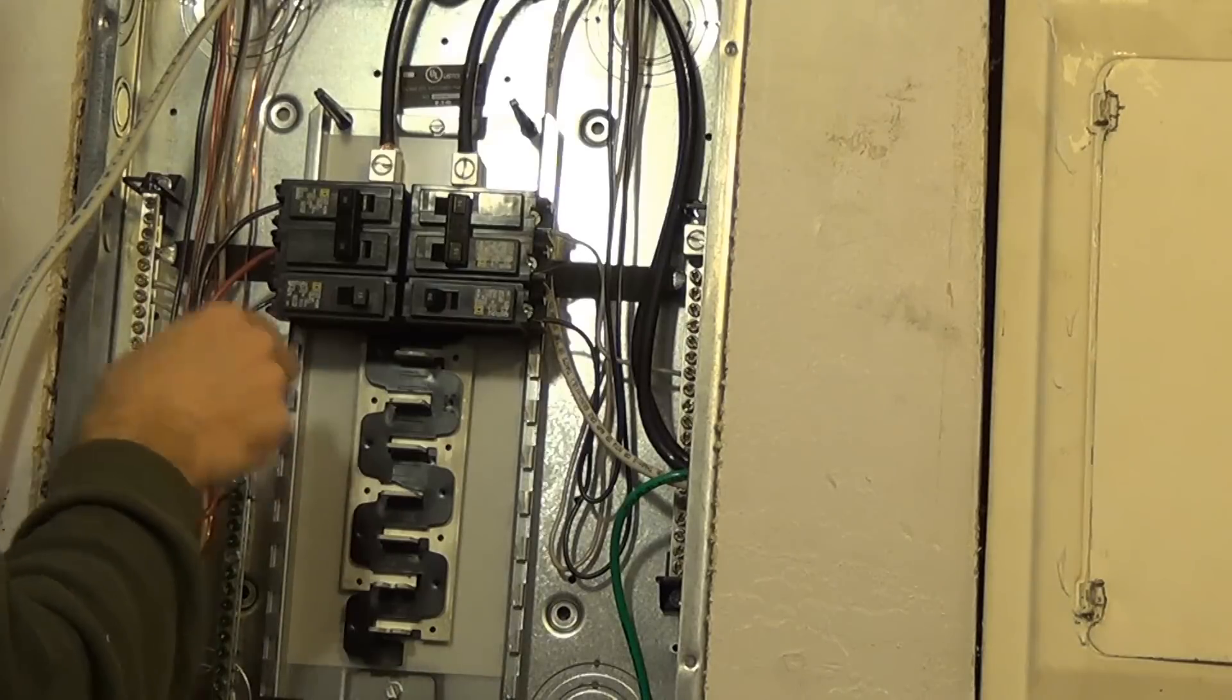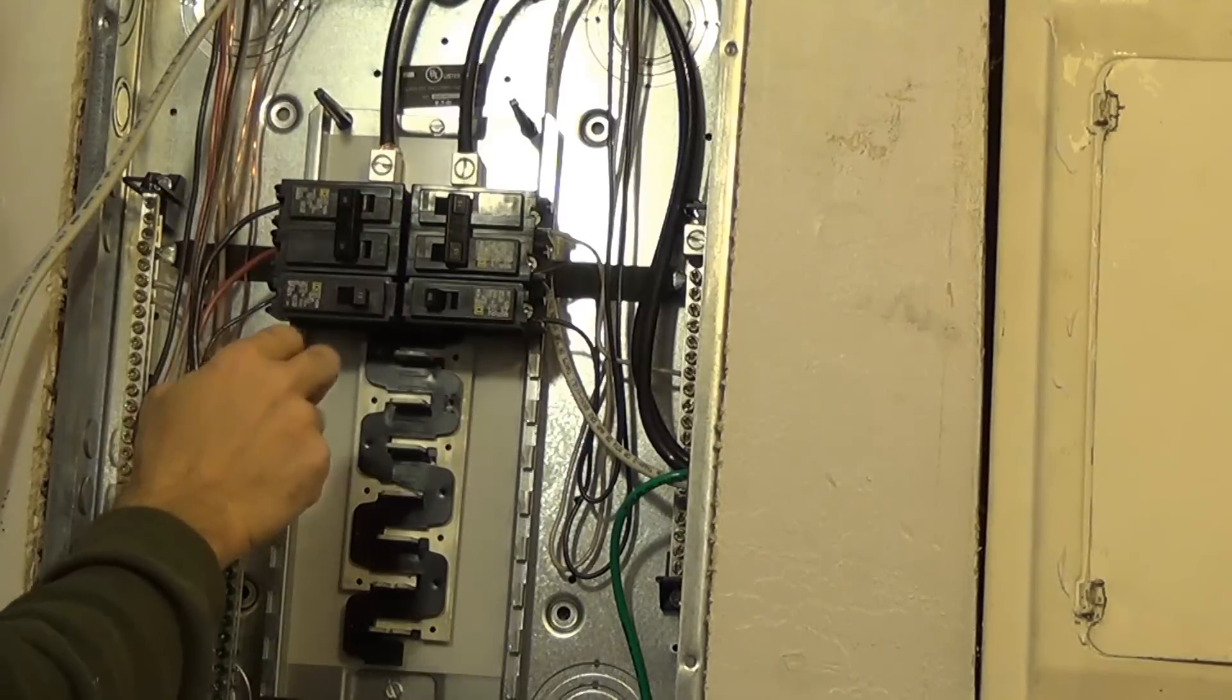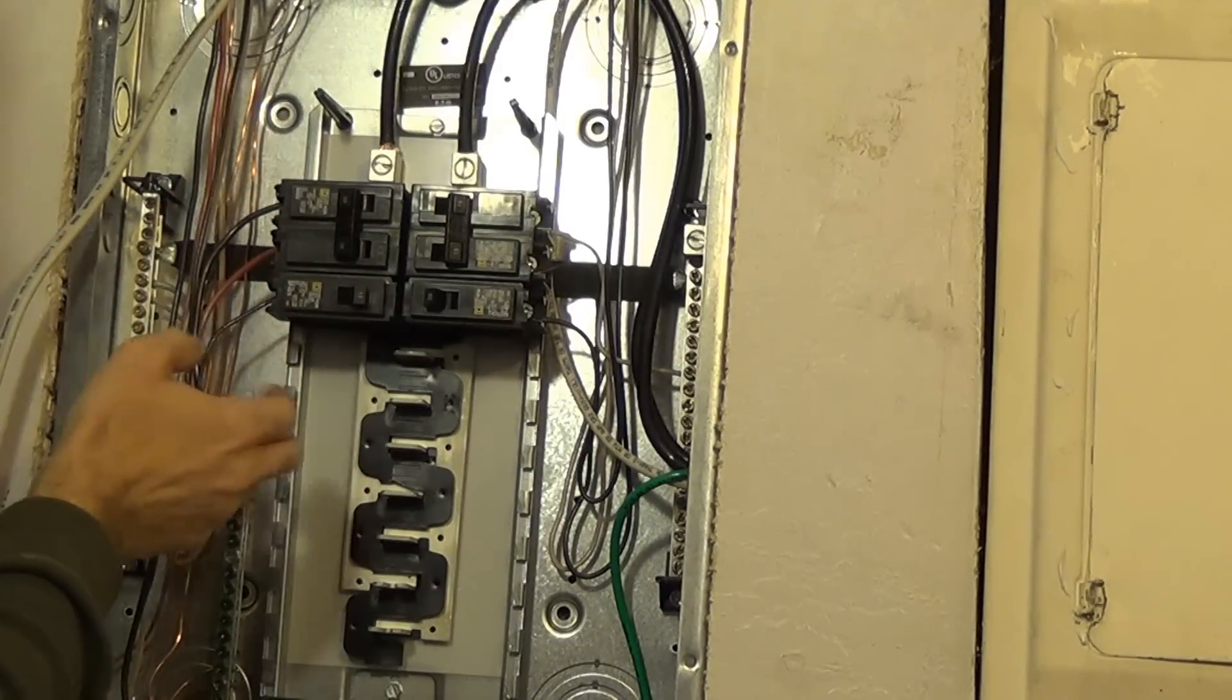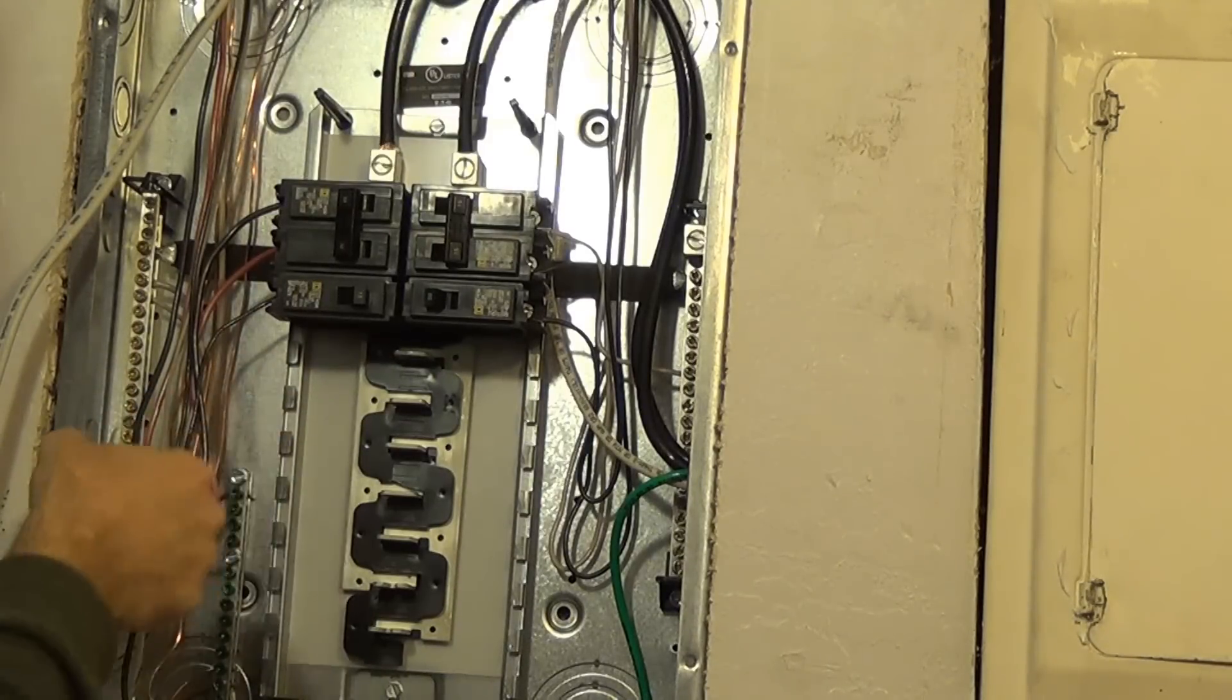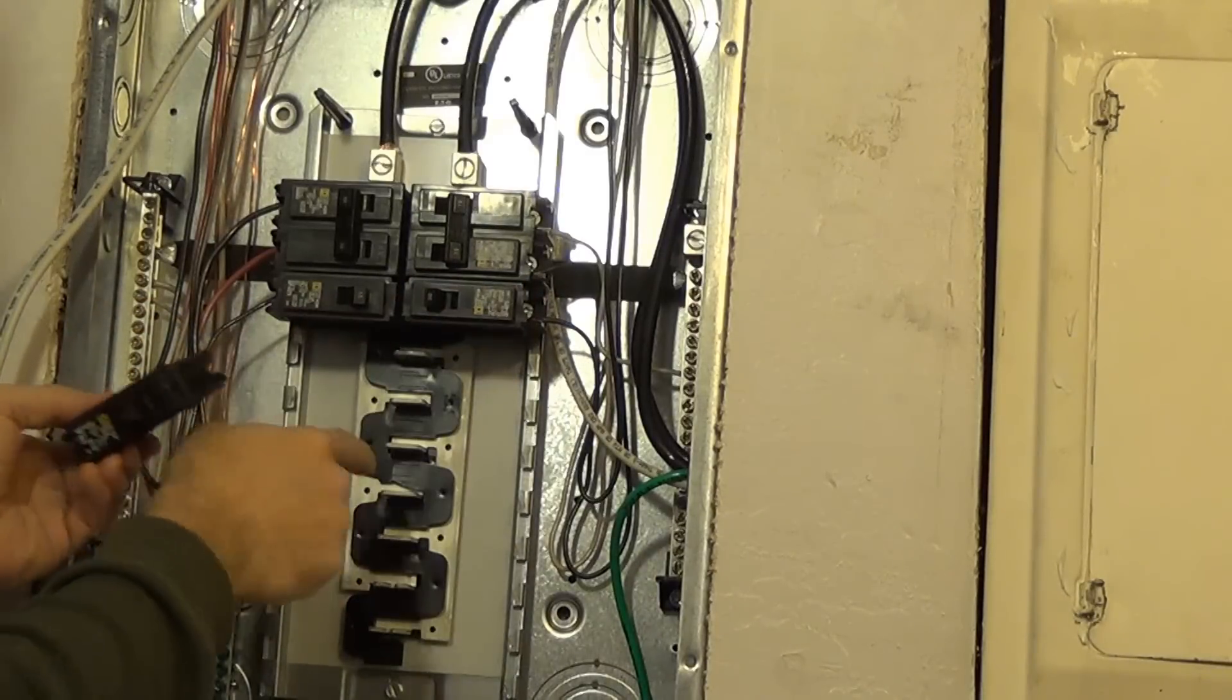The reason they do this is for your 240 volt. Since they're not in phase, if you hook one breaker into two of these, you will get 240 volts. That's why they do that. But it doesn't really matter for the 120 volt—it doesn't matter which one you connect into, it will work just as fine.